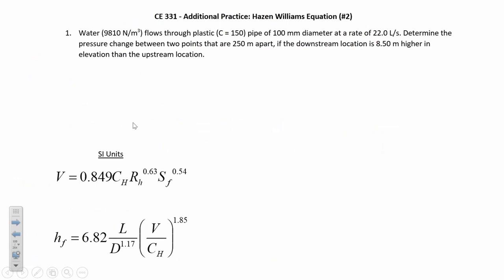This is the Hazen-Williams practice problem that you just solved. We have water flowing through a plastic pipe where we know the unit weight of water, the C value of the pipe, the diameter, and the flow rate. Anytime you have both the diameter and the flow rate, your mind should immediately jump to the fact that you can calculate the velocity relatively easily. That's important because if you want to calculate the head loss due to pipe friction, one of the direct input variables you need is the velocity. We've got the C value, the diameter, and the length of 250 meters — everything we need to calculate the head loss.